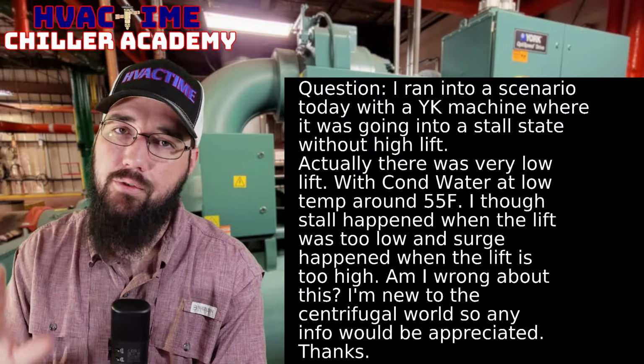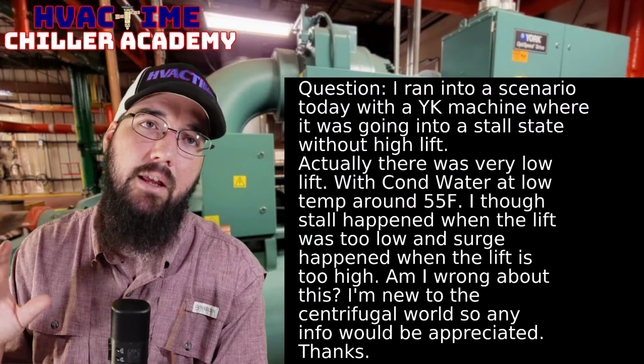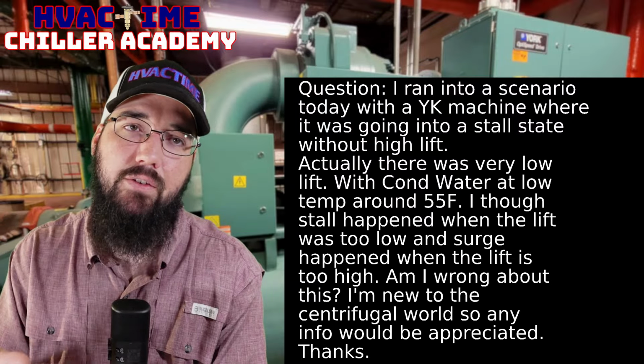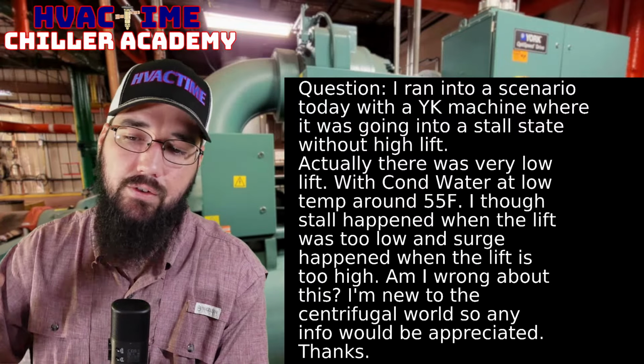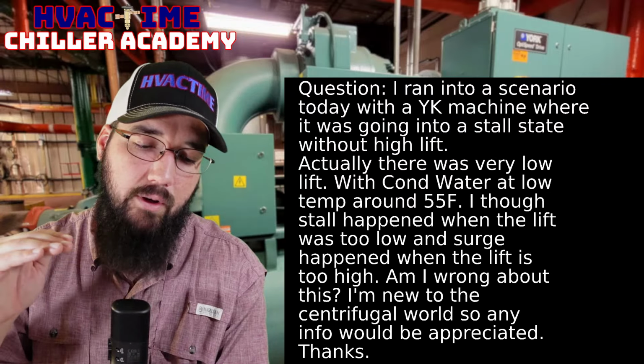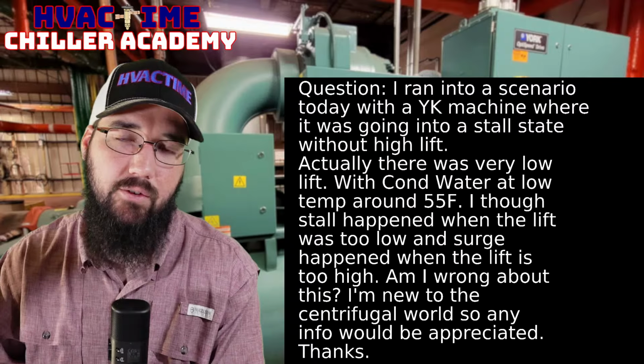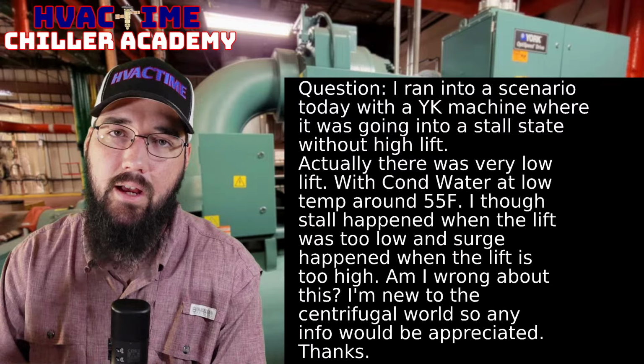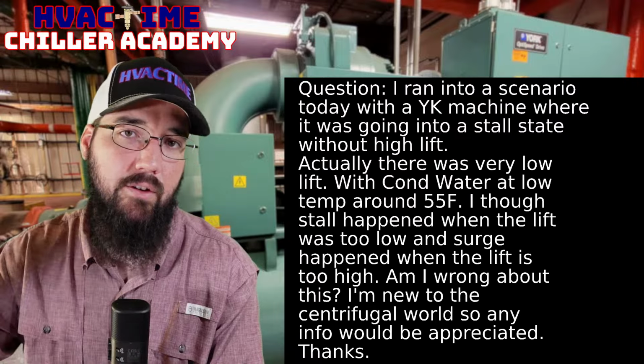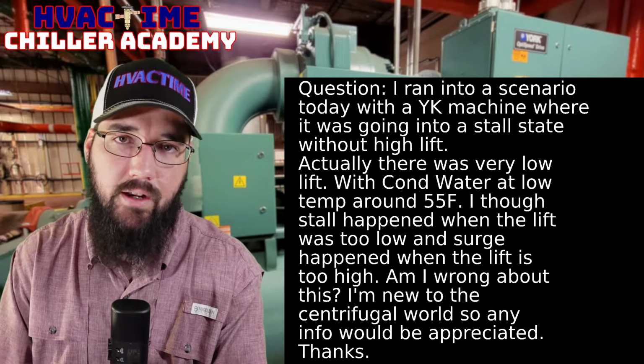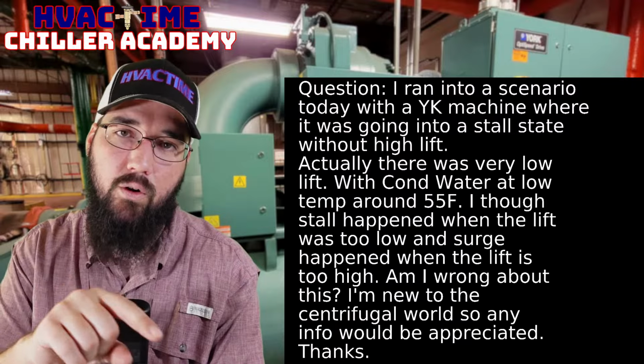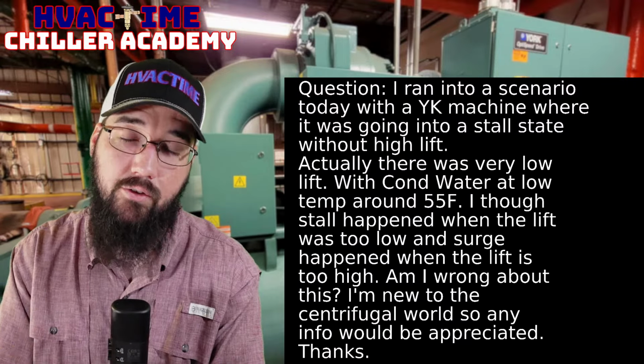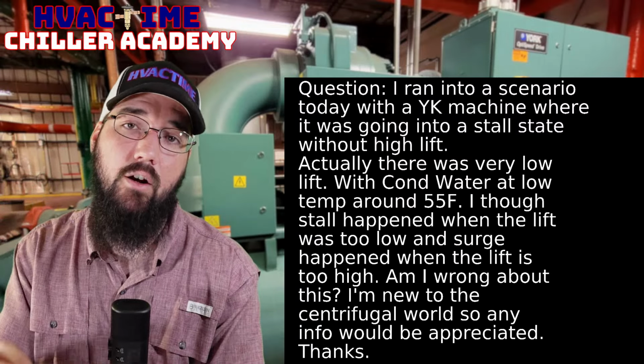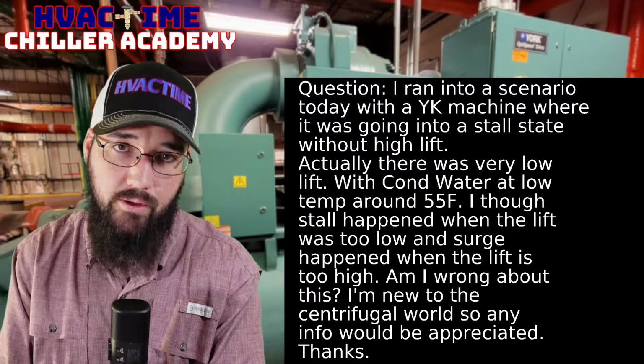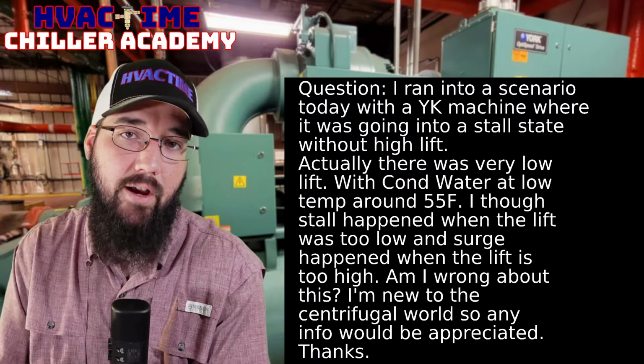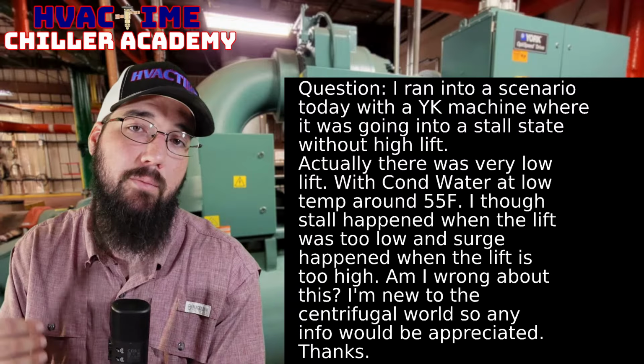And again, I go through all this in my course, but these things are built into how the machine stages. When we have an IGV VSD or VFD combo, that's why we see the inlet guide vanes go full open first and then we see the drive start to increase speed. All of that is tied back into what that surge graph looks like and what point we are on that graph. All that's built into the controller, even though you may not know it's there. You don't know that that is part of the algorithm controlling that. It is still part of what the manufacturer is using to control the machine either way. You just may not have access to it.